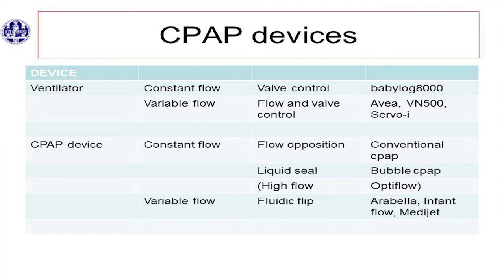The CPAP devices. There are different ways to divide them. This is the way I did it. The ventilators that can give CPAP and the CPAP devices. And the ventilators can be divided by giving constant flow, and that's how it works with flow opposition. It's a valve control. That's the old Babylog, and the Infant Star does that. So it's a constant flow. Even if the baby requires more flow by inspiration, you get some flow starvation, so that's a disadvantage. And also if you breathe out, you breathe against the flow, and you get an increased work of breathing.